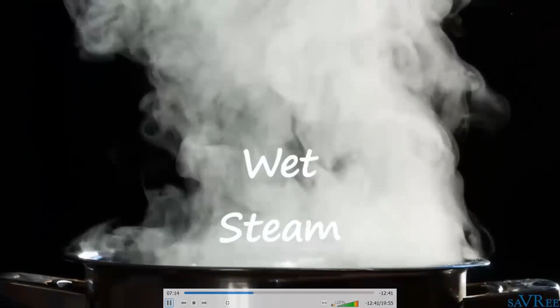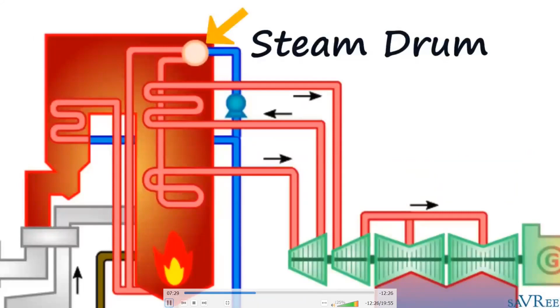In the steam drum, we'll begin to separate that moisture from the steam, sometimes using steam separators or steam cyclones, sometimes using an arrangement of baffles or a combination of both. We'll then send our steam to a superheater where we will really heat that steam up. As we discussed earlier, one of the ways to increase the efficiency of the basic Rankine cycle is to superheat the steam before it goes to the turbine. This is what you are seeing right now, superheating.